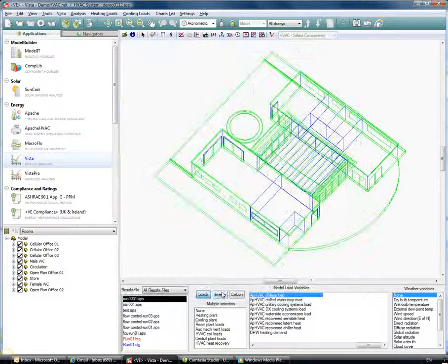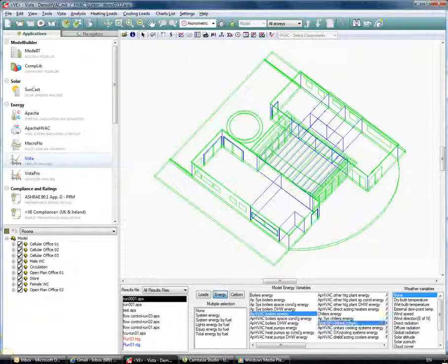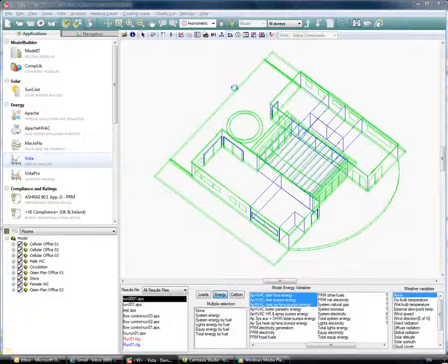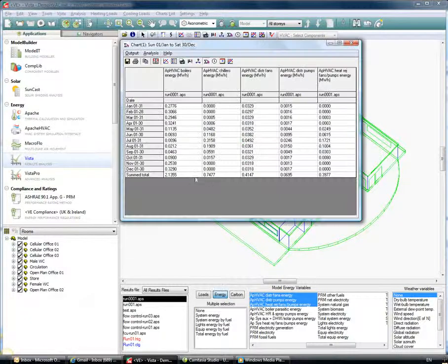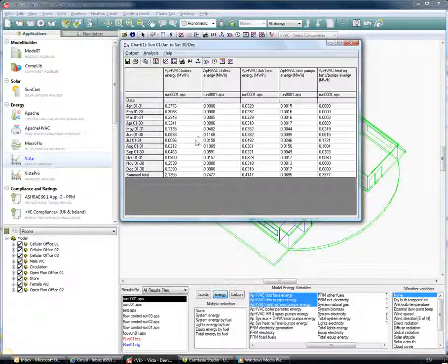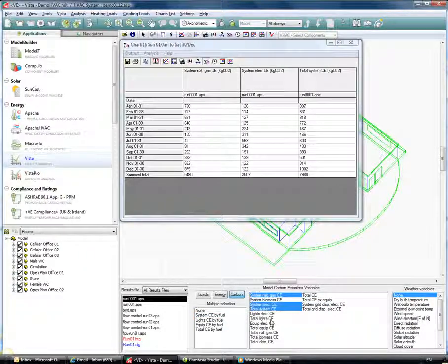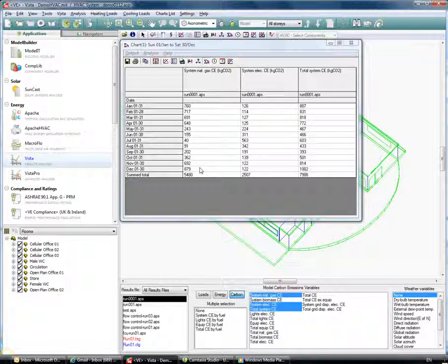I can also go into the energy section to look at Apache HVAC boiler energy, chiller energy, distribution fans, pumps, and heat rejection fans — easily graphed in monthly and summed totals. The monthly and annual totals table shows the different energies associated with each plant item throughout each month. We can also look at CO2 emissions: the split between fuels used for heating and cooling, including system natural gas CO2, system electric CO2, and total system CO2, represented monthly and as a summed annual total.